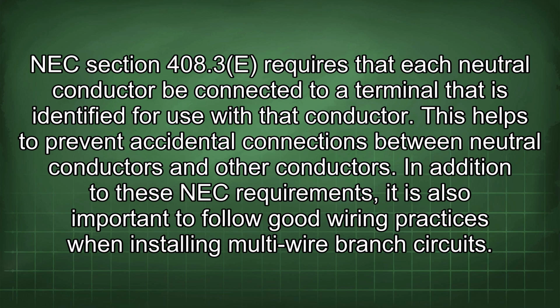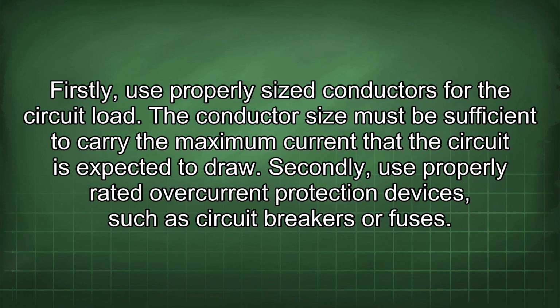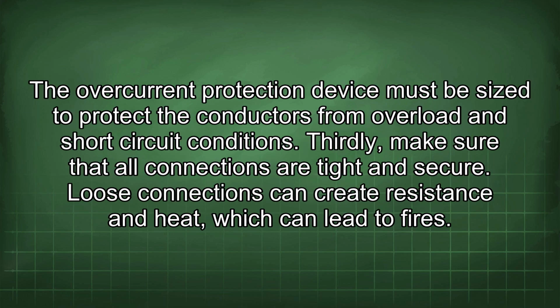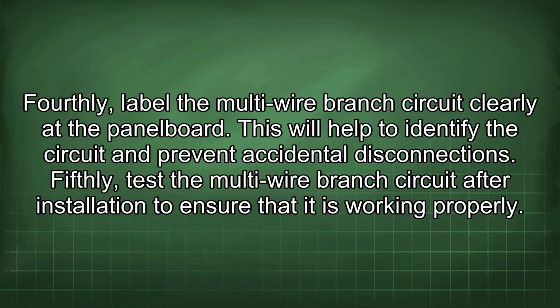In addition to these NEC requirements, it is also important to follow good wiring practices when installing multi-wire branch circuits. Firstly, use properly sized conductors for the circuit load. The conductor size must be sufficient to carry the maximum current that the circuit is expected to draw. Secondly, use properly rated overcurrent protection devices, such as circuit breakers or fuses. The overcurrent protection device must be sized to protect the conductors from overload and short-circuit conditions. Thirdly, make sure that all connections are tight and secure. Loose connections can create resistance and heat, which can lead to fires. Fourthly, label the multi-wire branch circuit clearly at the panel board. This will help to identify the circuit and prevent accidental disconnections.